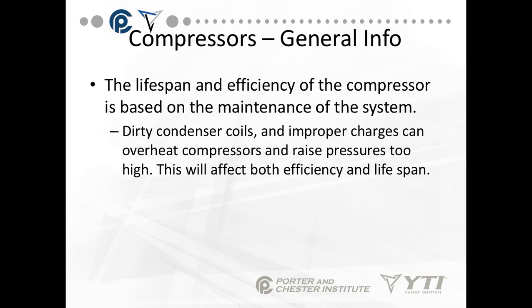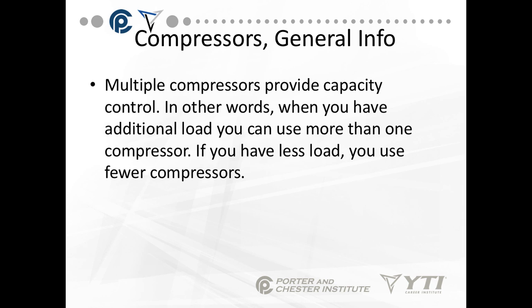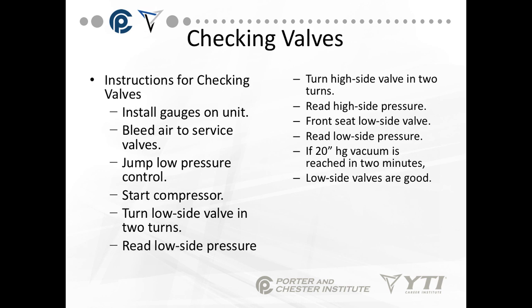The lifespan and efficiency of a compressor is 100% based on the maintenance of the system. Dirty condenser coils and improper charges can overheat a compressor and raise the pressures too high, affecting both efficiency and lifespan. The dirtier the coil, the hotter the compressor, the higher the amperages, and the more strain on the motor. Multiple compressors provide capacity control — you can control capacity with more than one compressor; if you have less load, you don't turn on all the compressors.